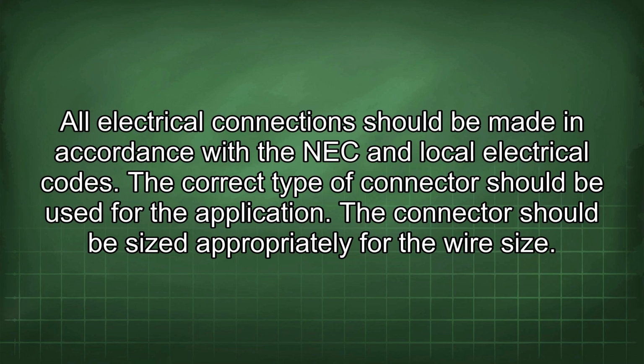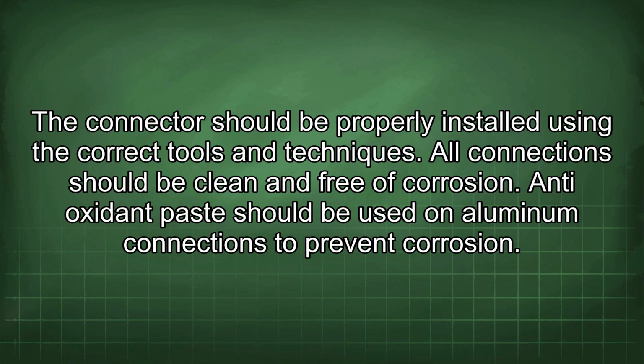The correct type of connector should be used for the application. The connector should be sized appropriately for the wire size. The connector should be properly installed using the correct tools and techniques. All connections should be clean and free of corrosion. Antioxidant paste should be used on aluminum connections to prevent corrosion.